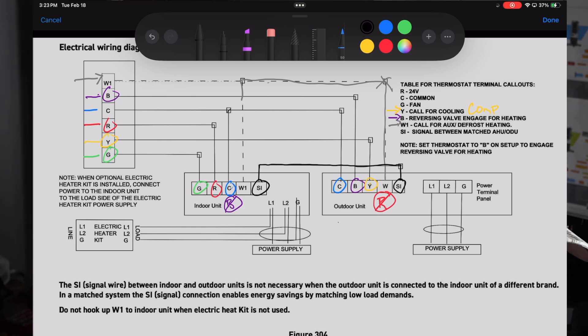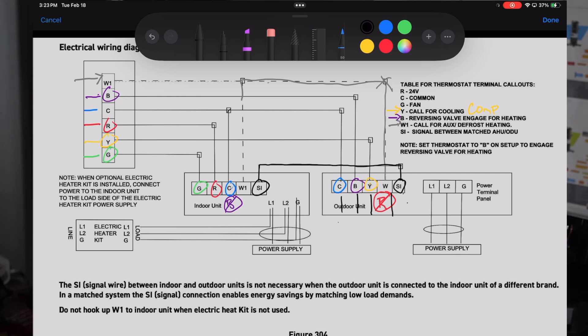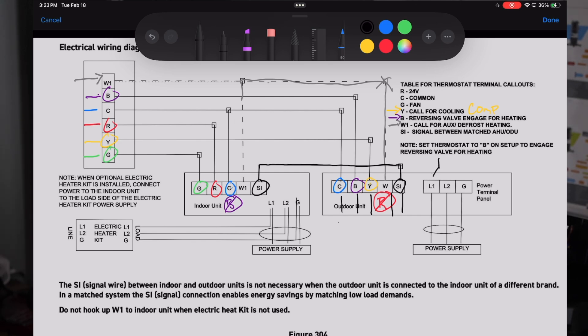Everything else is pretty much going to stay the same. No matter what happens, these are the five terminals you're going to have on your Friedrich Breeze outdoor unit. They're the only five terminals you have to hook up from your outdoor unit to your indoor unit or to your thermostat depending on which wire it is. You have C for common, B for reversing valve, Y for your call for compressor, W for your backup heat during defrost - remember that's only for electric heat. If you have gas backup heat, do not hook a wire on W on your outdoor unit. And then the very last wire is that SI terminal, only to be hooked up if you have the matching Friedrich Breeze air handler.